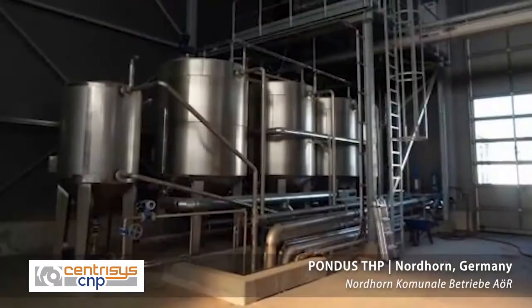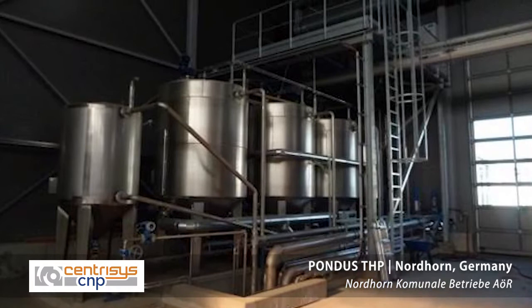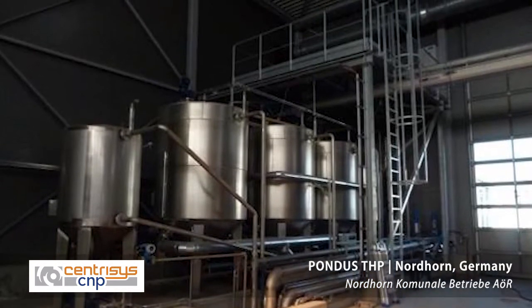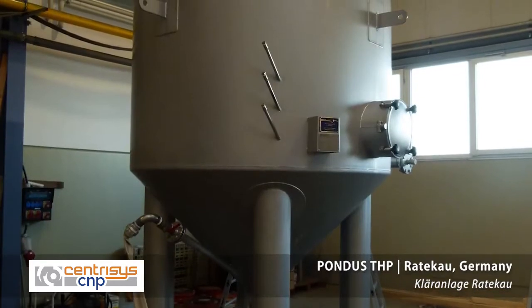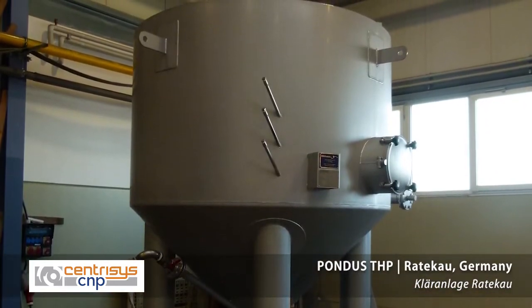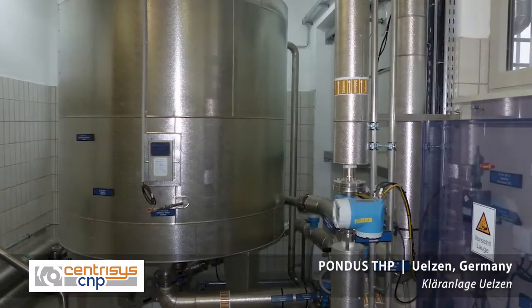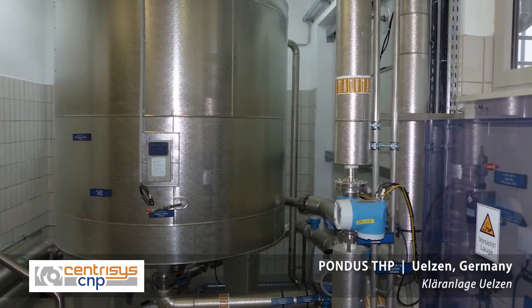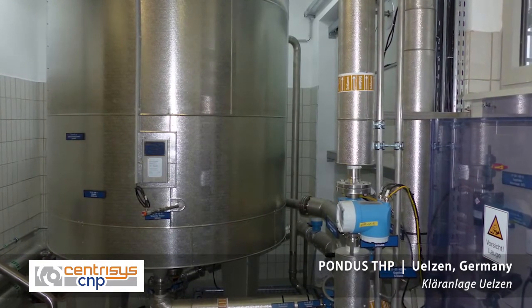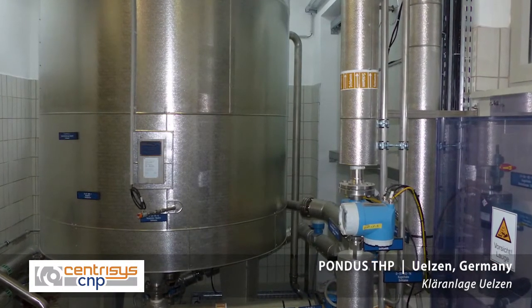And the last 2-3 years, the main driver for the technology was really reduction in biosolids. Just like what we see on the phosphorus side, when you hydrolyze the sludge, you get better digestion performance in an anaerobic digester, which means you lose more organics in the digester. And that typically leads to better dewaterability of your cake, with a high ash content, less organics. And so you end up in your plant with fewer biosolids, which reduces your disposal costs. That was a big driver, is still the main driver in Germany, and is a similar driver in the United States.